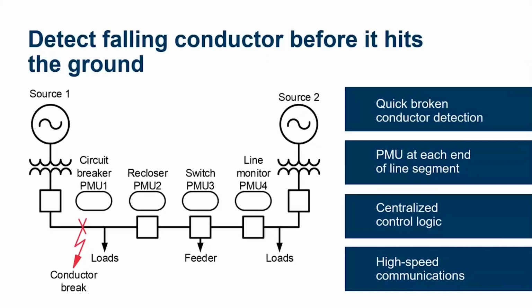The way this works is that we have to have a PMU, a phasor measurement unit, at each end of the protected line. So think of this as almost like a line differential type of scheme, because we're looking at data measured by both of those PMUs, comparing them, and bringing that into centralized logic to make a decision. This scheme requires high-speed communication, so we need relatively low latency and high data throughput, because we're sending a lot of synchrophasor data to a centralized location.